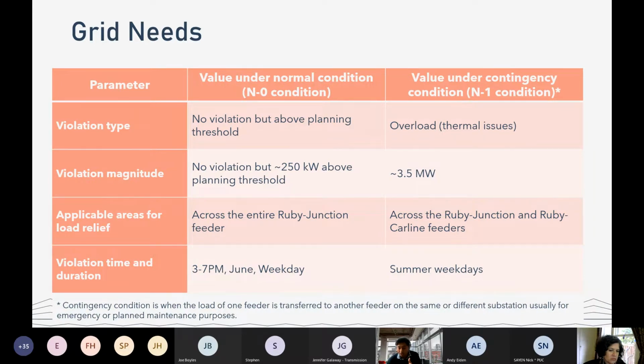And behold, on the column to the right, there are thermal issues when we assume a contingency condition, meaning we have to serve customers with a different feeder, so Ruby Junction is down and the load is shifted onto Ruby Carline. Ruby Carline would then have significant thermal issues, adding up to about 3.5 megawatts. So the hope is that we're alleviating about 250 kilowatts on the Ruby Junction feeder and about 3.5 megawatts across both Ruby Junction and Ruby Carline.